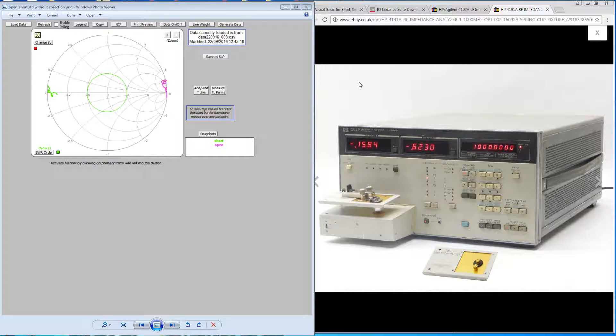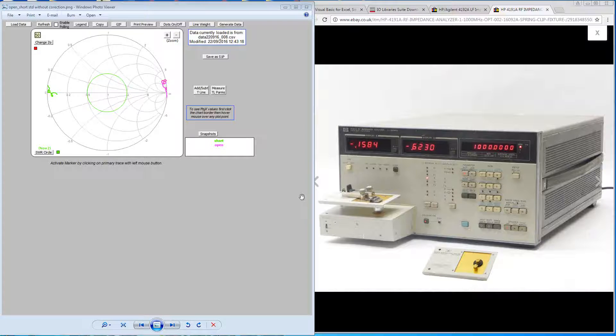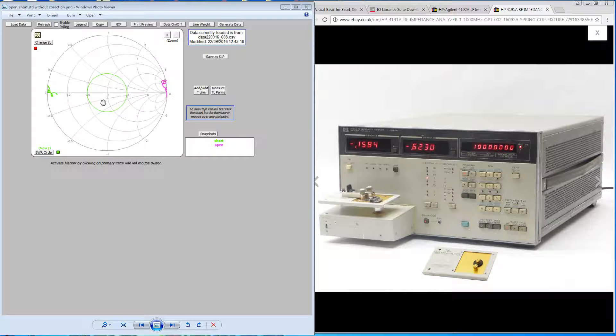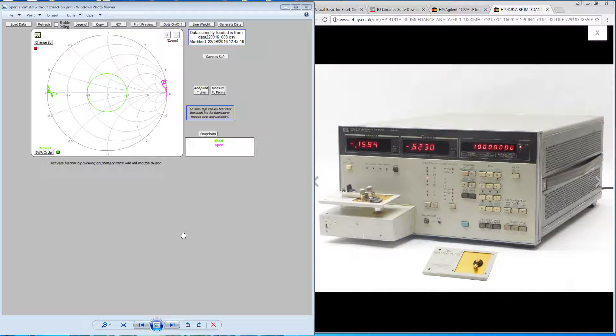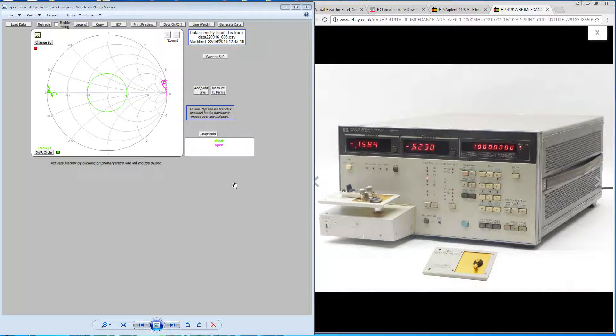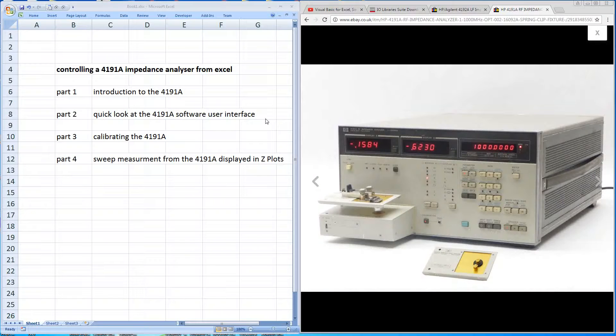On the left here you'll see an example plot that you can extract from the machine. It shows an open and a short plotted onto a Smith's chart. This is displayed in Z plots. So this is the ultimate goal to show you how to achieve this from within the machine.